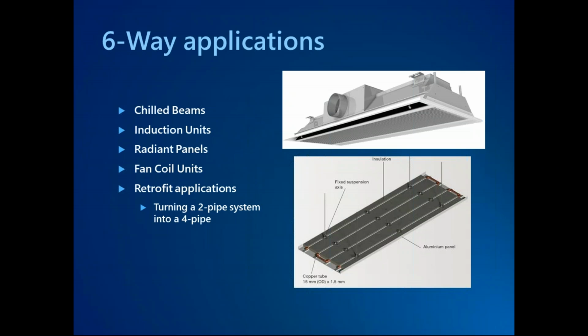Some of the other types of applications on top of the chilled beams would be a radiant panel. It could be the radiant fins, or even a traditional fan coil unit, utilizing a single coil as opposed to two coils for your four-pipe chilled beam.